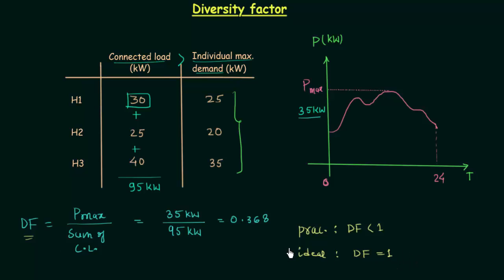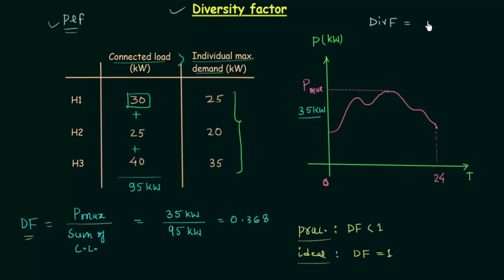Now we will talk about diversity factor. Diversity factor is very important. Of all the different things we have studied so far, diversity factor and plant load factor are the two most important. You have to focus more on plant load factor and diversity factor because they play a very important role in reduction of cost. Diversity factor is equal to the ratio of the sum of individual maximum demands to the maximum power demand.